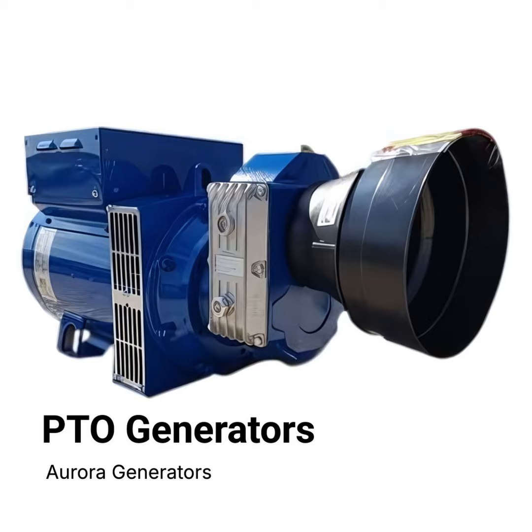I've seen these insulation classes mentioned, like Class H or Class F. What do they signify? Those letters represent standardized temperature ratings for the insulation materials themselves. Class H, for example, can withstand higher temperatures than Class F before it starts to degrade. So, a Class H system uses materials inherently more heat resistant. This gives the designer options for how hard they want to run the alternator.